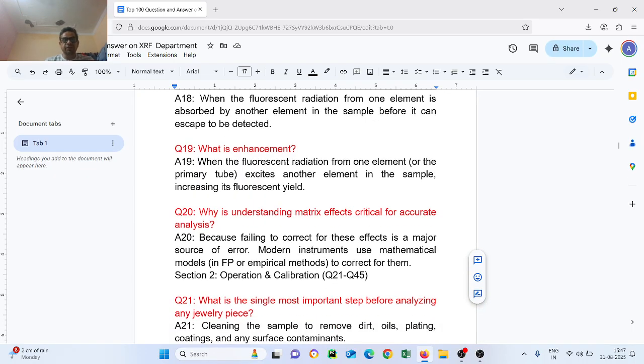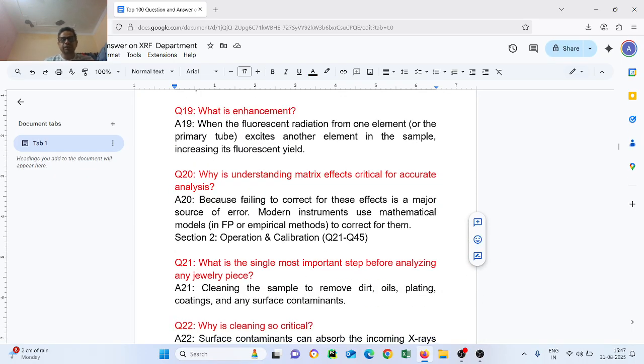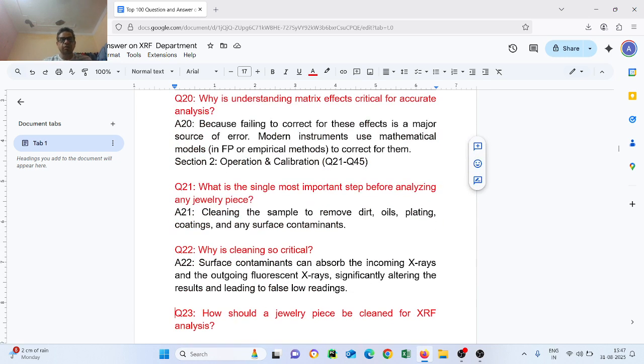Now question number 21. What is the single most important step before analyzing any jewelry piece? The answer is cleaning the sample to remove dirt, oil, plating, coating and any surface contaminant. Question number 22. Why is cleaning so critical? Surface contaminants can absorb the incoming X-ray and outgoing fluorescent X-ray, significantly altering the result and leading to false low readings.